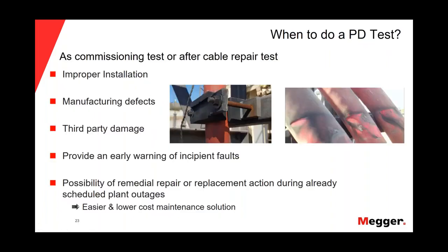So when do we use partial discharge? Well, we can use partial discharge as commissioning tests or after cable repair tests. And the goal is to find improper installation, manufactured defects, or third party damage. Partial discharge is especially good to find poor workmanship issues or manufactured defects, or also installation problems.